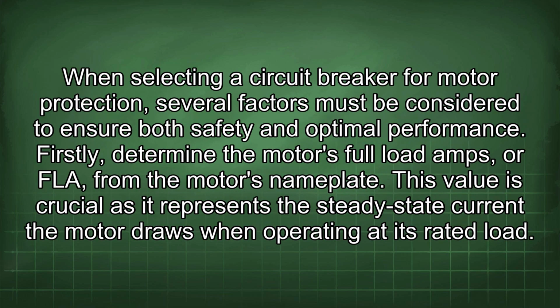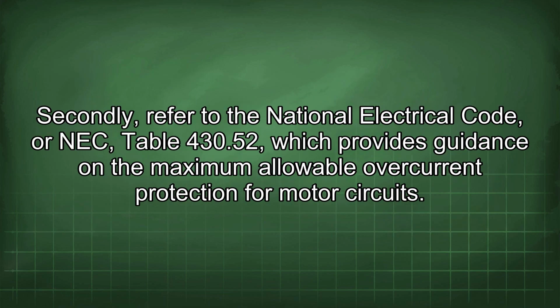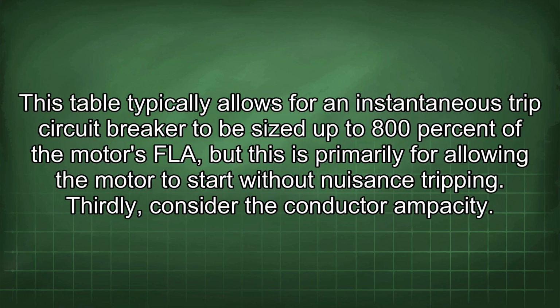When selecting a circuit breaker for motor protection, several factors must be considered to ensure both safety and optimal performance. Firstly, determine the motor's full load amps, or FLA, from the motor's nameplate. This value is crucial as it represents the steady-state current the motor draws when operating at its rated load. Secondly, refer to the National Electrical Code, or NEC, Table 430.52, which provides guidance on the maximum allowable overcurrent protection for motor circuits. This table typically allows for an instantaneous trip circuit breaker to be sized up to 800% of the motor's FLA, but this is primarily for allowing the motor to start without nuisance tripping.